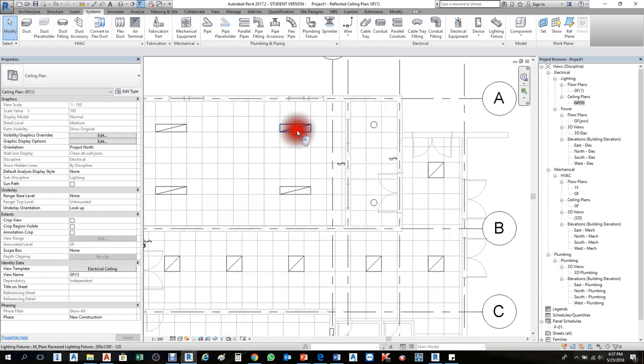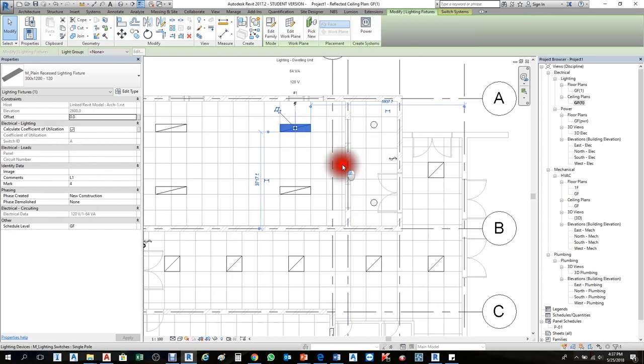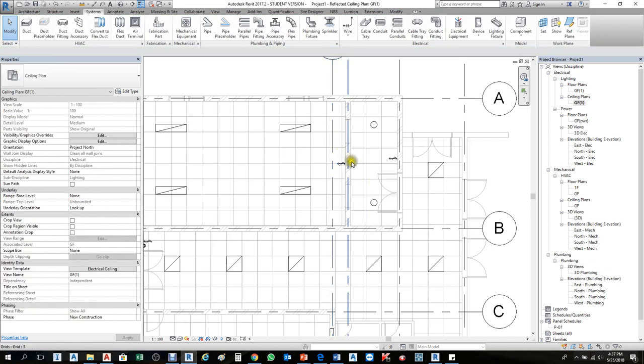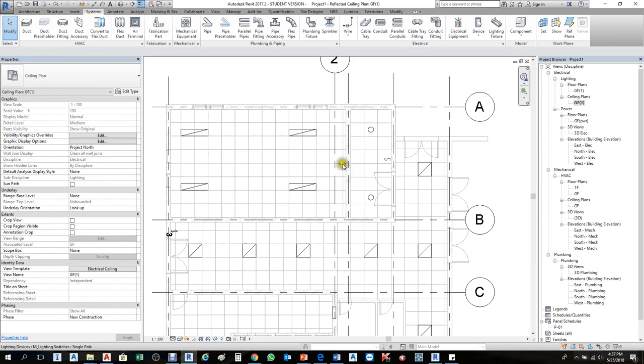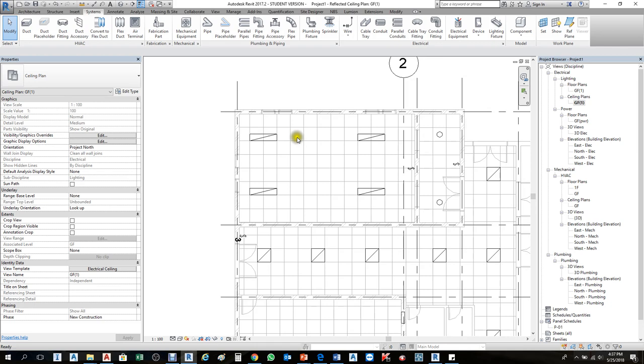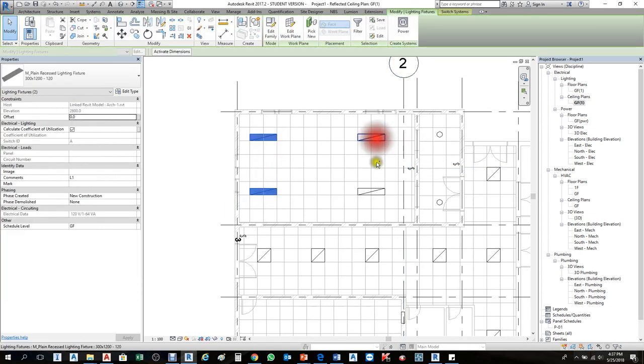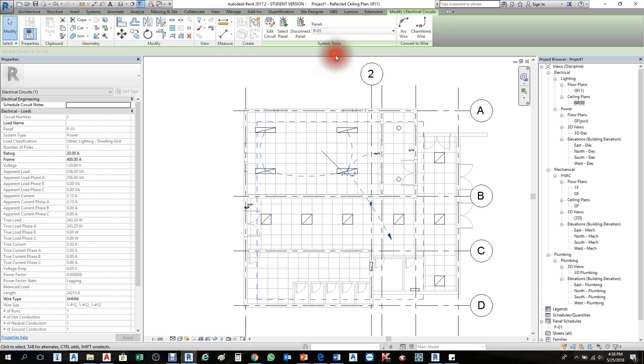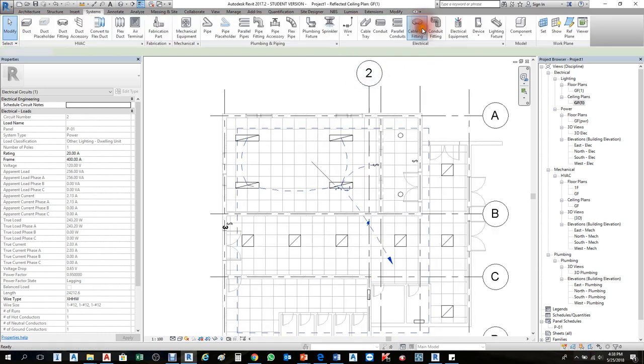Select all lights — the only thing remaining is Power, since all of them go to one panel. To see which lighting a switch controls, hover your mouse over the switch and press Tab once. It will highlight which lights that switch controls. Now I'll create the power system. Select all lighting fixtures and the switch itself, since all need panel power. Click Power — it asks you to choose the panel name. Choose Panel 1, then choose Chamfer or Arc for the wiring style.